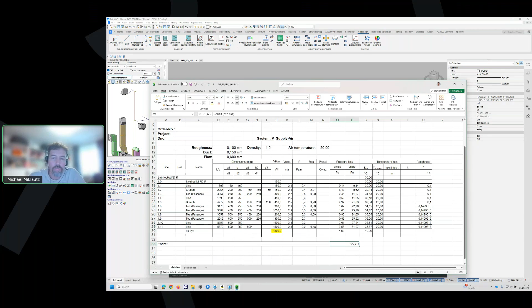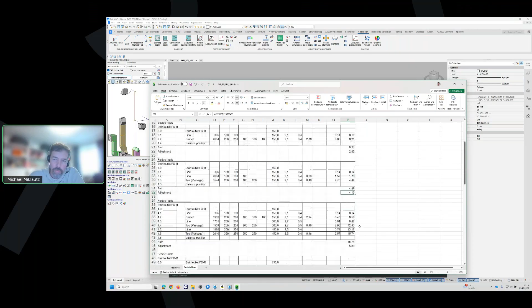On the other hand, all beside lines are always calculated. In heating, the result will be a valve setting, a valve selection. But here I can see the adjustment value. So I have decided in this main line, or in this subline, in this beside line, I have to adjust 2.8 Pascal. Then I need 4 Pascal. Then I need 5 Pascal. Whatever I have to do.